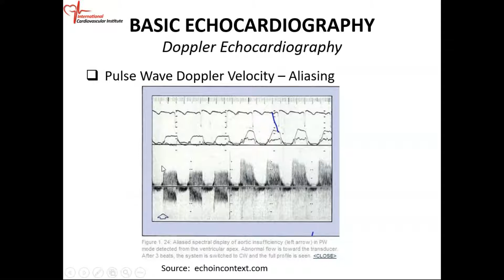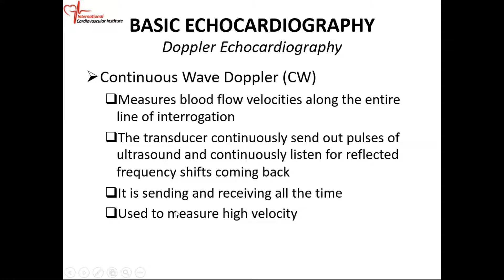So continuous wave Doppler measures blood flow velocity along the entire line of interrogation. When we talk about continuous wave Doppler, it's continuously sending out signal and receiving signal. There is no wait for reflected signal. The transducer continuously sends out ultrasound and continuously listens for the reflected frequency shifts coming back. Okay? It's sending and receiving at all times. So if you have high velocity to measure, you use your continuous wave Doppler. We use continuous wave Doppler to measure high velocity flow.